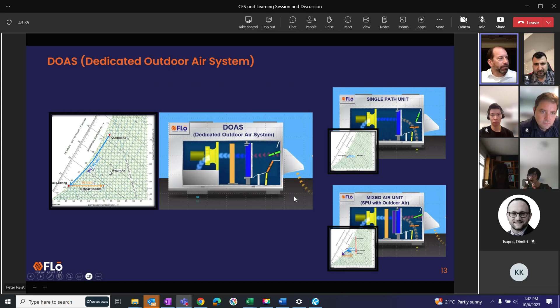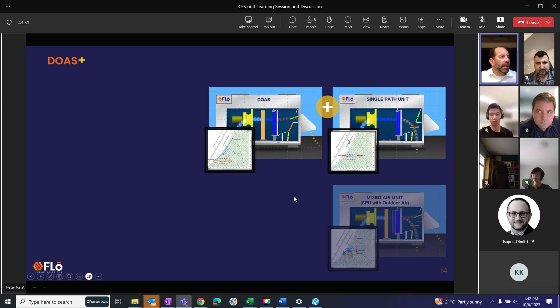Now a DOAS unit, you can't have that on its own because it's only doing outside air. So we find DOAS units often put with recirculating units. That's those RTUs I was talking about before. And you have this guy dealing with the outside air, and you have this guy dealing with the recirculating air, right? Makes sense.